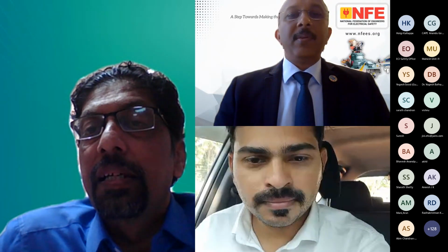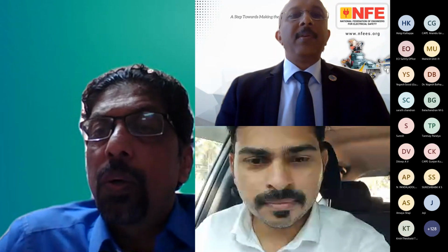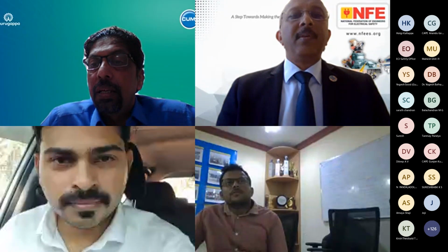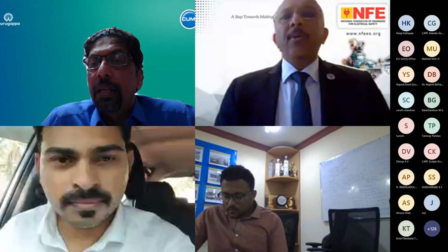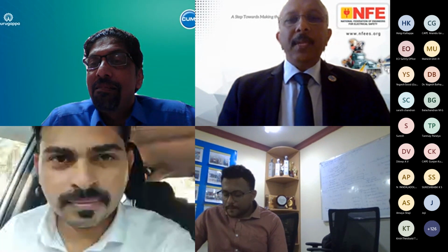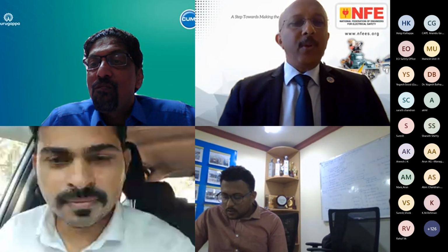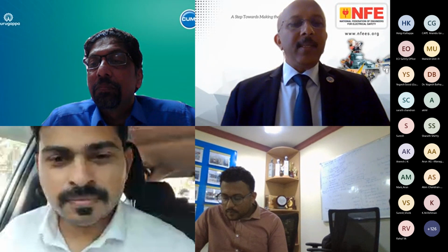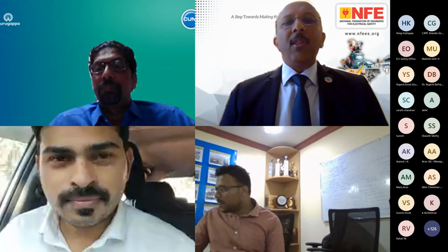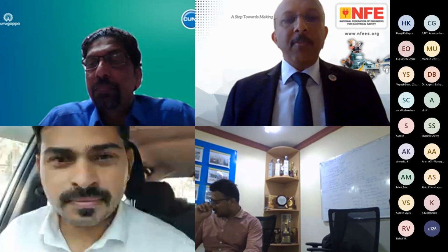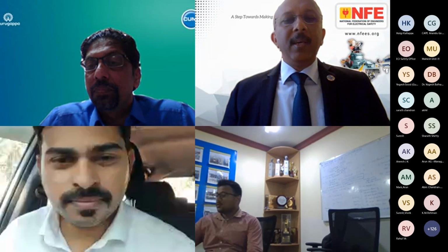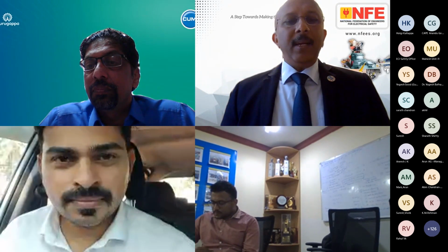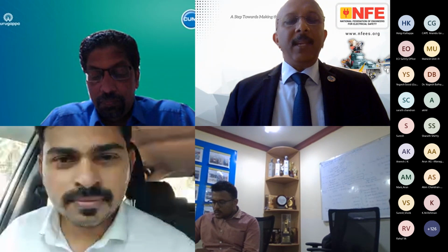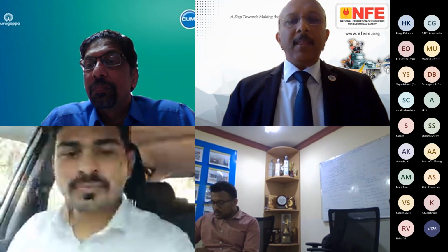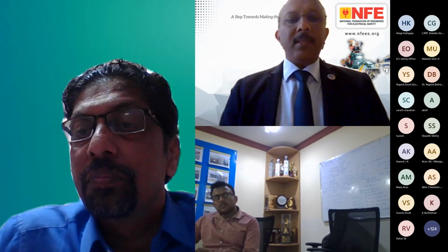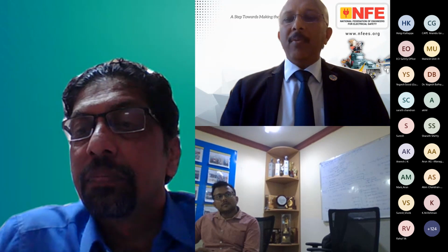Right, thanks. How do we calculate fault loop impedance manually? You know the transformer size, you know the percentage impedance of the transformer, you know the length and size of the conductors, and you calculate the resistance of all these together. The most important is the resistance of the line conductor, because we take it very carefully, whereas the metallic return path resistance calculation is a little bit tricky.